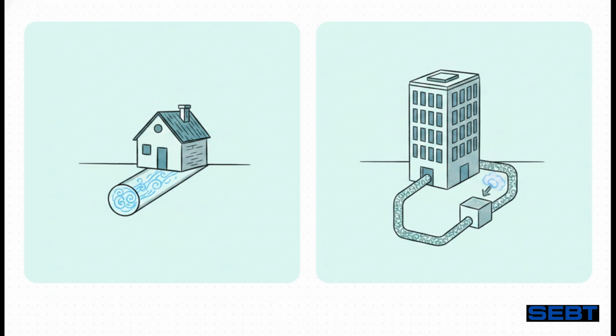Like the Cambridge Public Library, massive multi-unit public buildings often go a different route. They use fluid-based systems that pump a glycol water mixture in a closed underground loop. The fluid gathers temperature from the soil, then exchanges it with the building's air through a heat exchanger. This entirely separates the soil from the breathing air, completely preventing any humidity or bacterial risks.